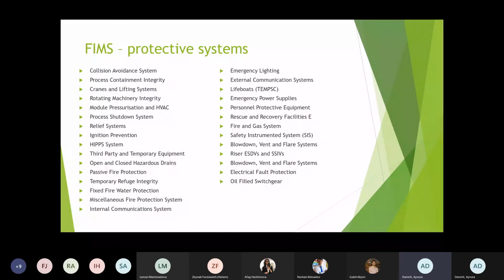And risers and ESDVs, it's also part of FIMS, to prevent or reduce the loss of inventory released in the event of a major accident hazard. This is achieved by providing suitable and reliable barriers to isolate the incoming fluid, the pipeline inventories, and to isolate the topsides process and utilities in defined areas in order to minimize the potential for incident escalation. Blowdown, vent, and flare systems provide facilities for rapid removal of hydrocarbon inventory from isolated sections of the facilities to a safe disposal point to reduce the potential for escalation of a major accident hazard.